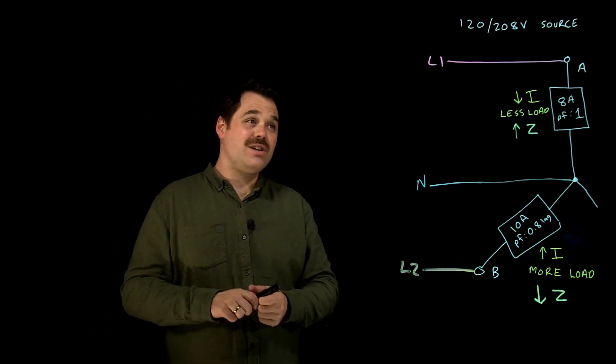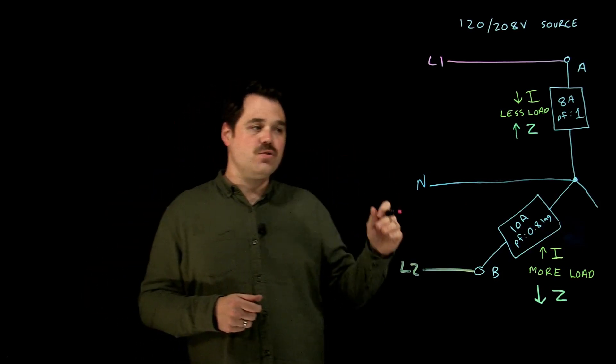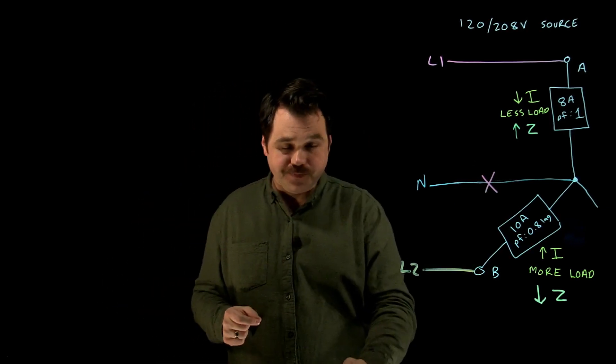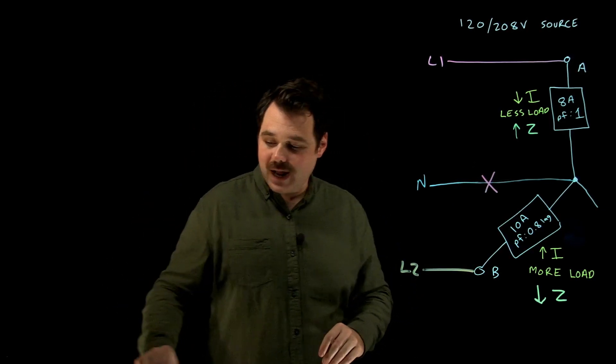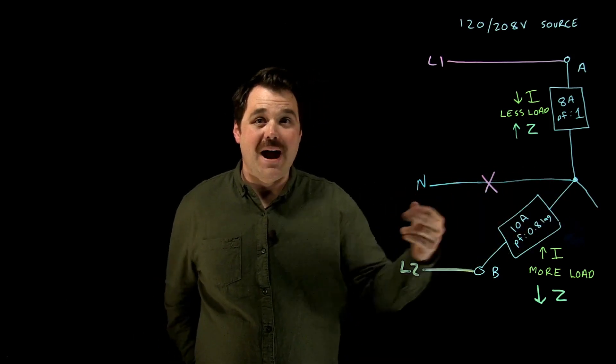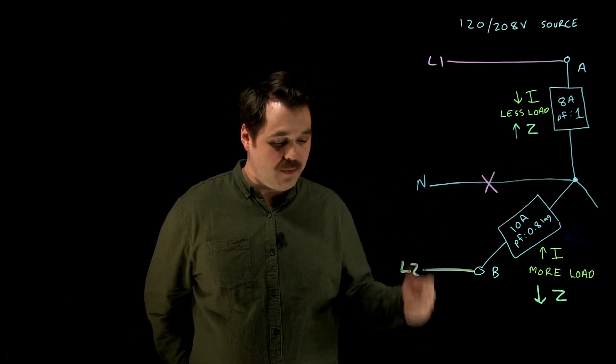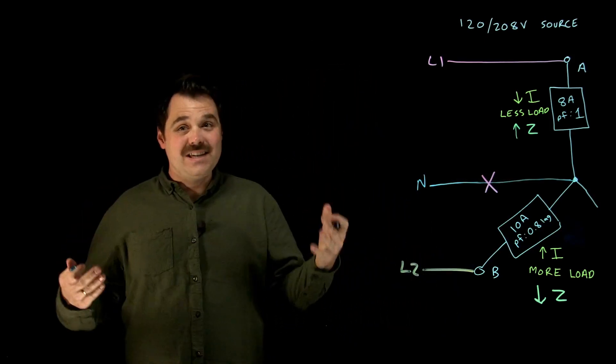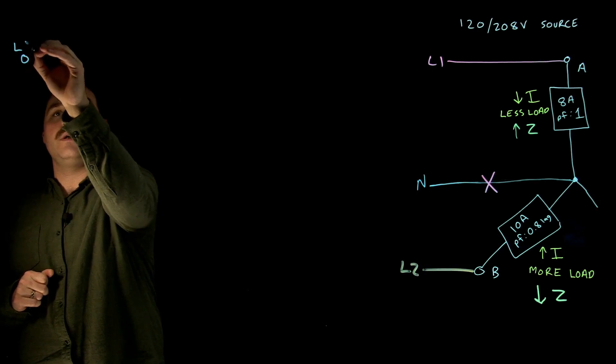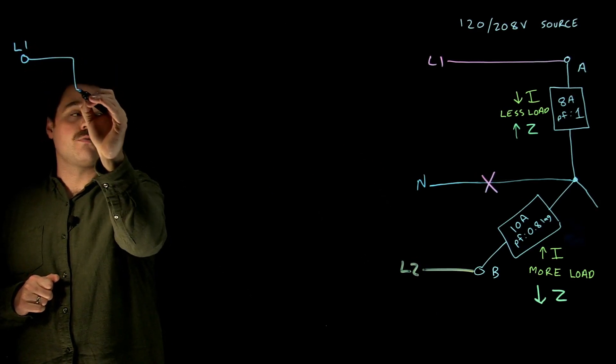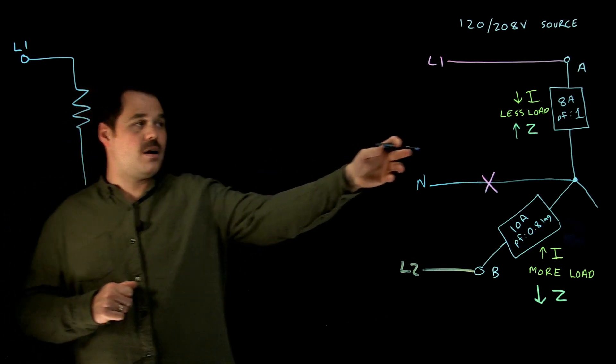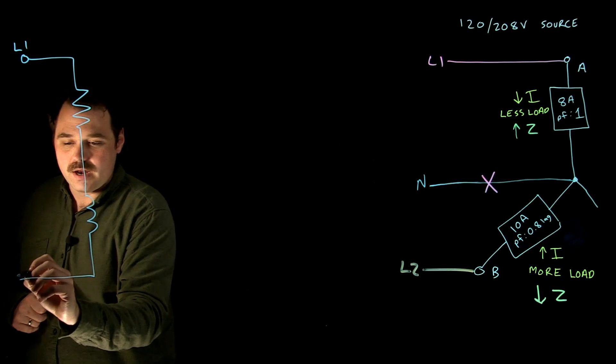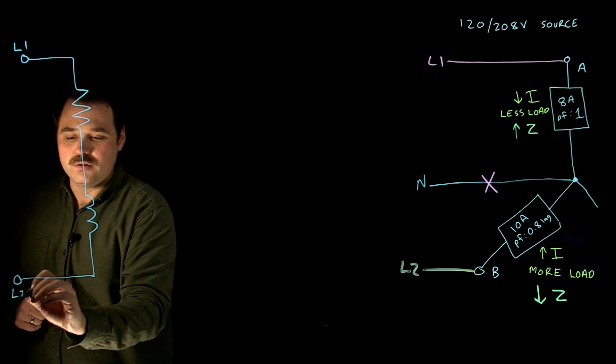So my question here is this: what happens when the neutral breaks, when I get a break on that neutral conductor? Well, effectively what happens is, because we no longer have that path for unbalanced load to travel back, we essentially develop a series circuit starting with line one, going through that resistive load with the power factor of one, and going through that inductive load back to line two.